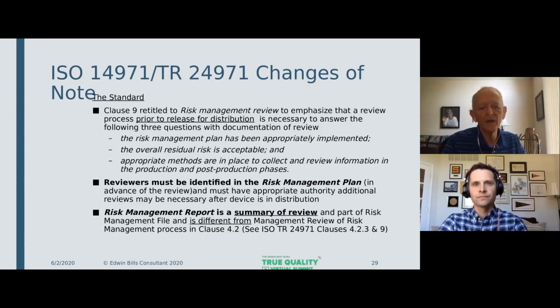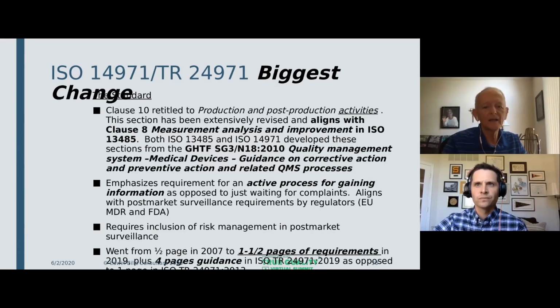Clause 9, retitled a risk management review. You now have to identify in your risk management plan who is going to do the review, when it's going to be done, and then it's got to answer the 3 questions, and then you issue a report based upon the results of that review. Okay, Clause 10, we talked about that as being production and post-production activities. It aligns with Clause 8 in 13485. Both of those were aligned with the post-market surveillance requirements by the FDA and the EU.